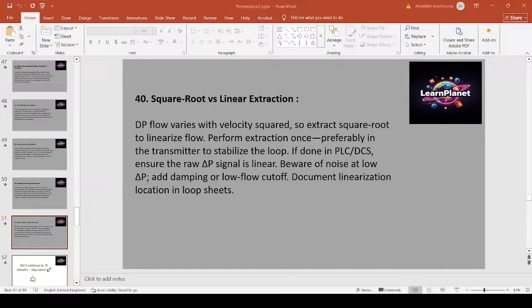Because delta P is proportional to velocity squared, square root extraction linearizes flow for control and display. Perform extraction once. Usually the transmitter does it so that the DCS receives linear flow values and filtering is consistent. If extraction is done in the controller, keep the raw delta P available for diagnostics and troubleshooting. At low delta P, noise can dominate. Use low flow cutoffs or damping to avoid spurious flow readings. Example, configure the DP transmitter to output linearized flow to the DCS and log raw delta P as a diagnostic tag.